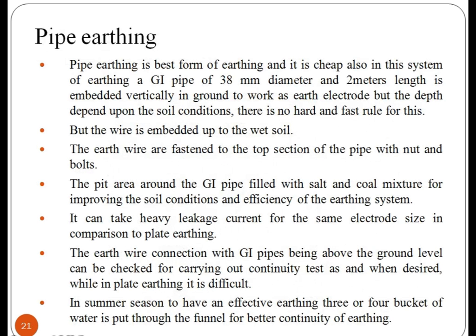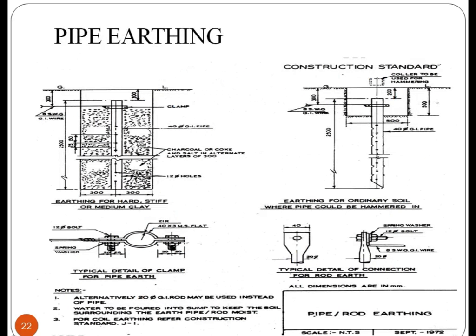In pipe earthing, a GI pipe of 38 mm diameter and 2 meter length is embedded vertically in the ground to work as the earth electrode, but the depth depends upon the soil condition and there is no hard and fast rule for this. The earth wires are fastened to the top section of the pipe with nuts and bolts. You can see the diagram of pipe earthing where the pit area around the GI pipe is filled with a salt and coal mixture for improving the soil condition and efficiency of the earthing system. It can take heavy leakage current for the same electrode size in comparison to plate earthing.